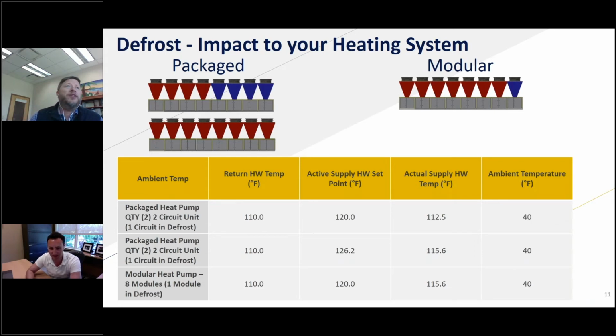I would just say that the amount of humidity that's in the air is going to drive how much or how little we're going to be defrosting. So you can't just simply look at anytime you're below 50 degrees outside, I know I'm going to be defrosting this amount of time. It's not that simple because it's a function of how, as we get colder and colder, at 0 degrees, there's less moisture in the air typically than there is at 30 degrees, right? So there's multiple factors that determine how often or how much we're defrosting, especially if you're getting into more sophisticated defrost versus that timed version.